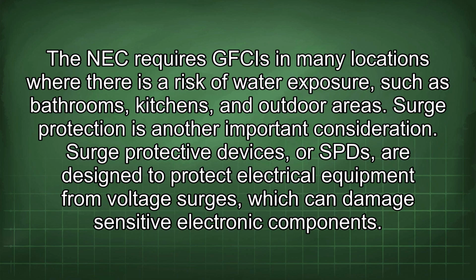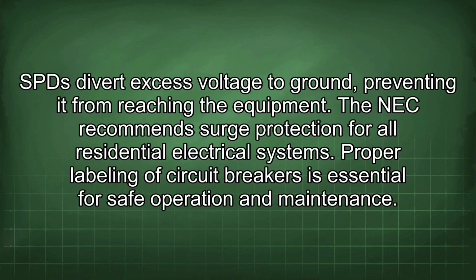Surge protection is another important consideration. Surge protective devices, or SPDs, are designed to protect electrical equipment from voltage surges, which can damage sensitive electronic components. SPDs divert excess voltage to ground, preventing it from reaching the equipment. The NEC recommends surge protection for all residential electrical systems.